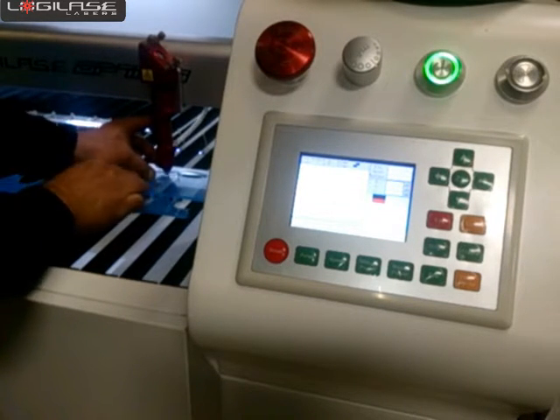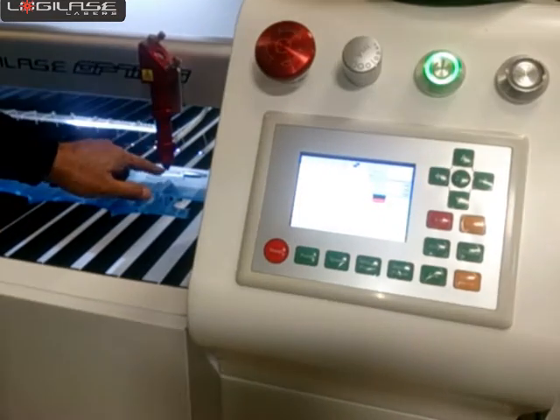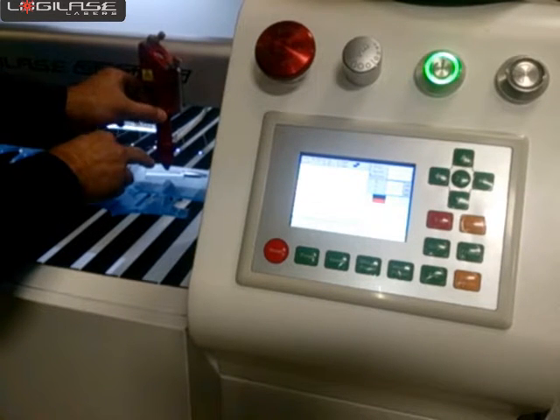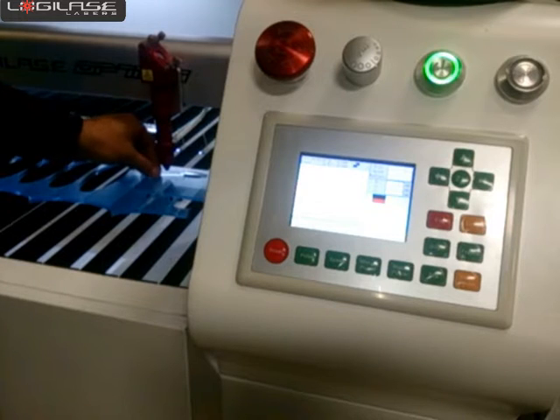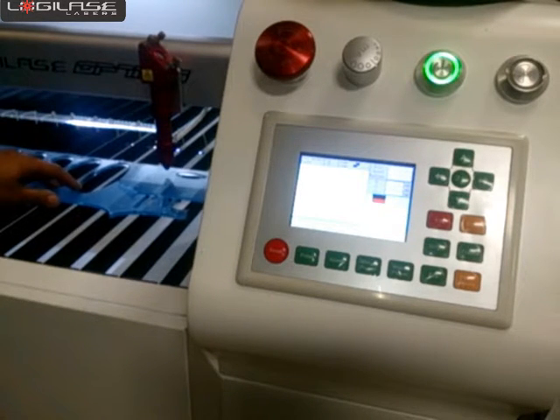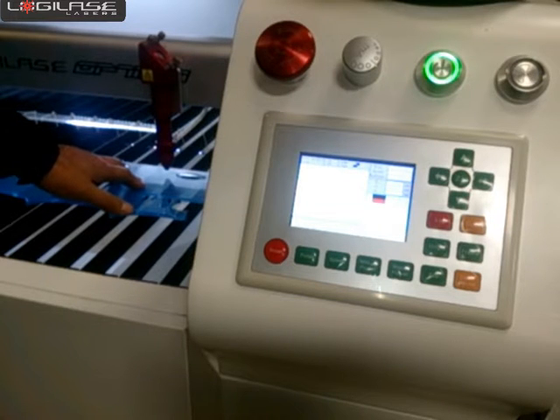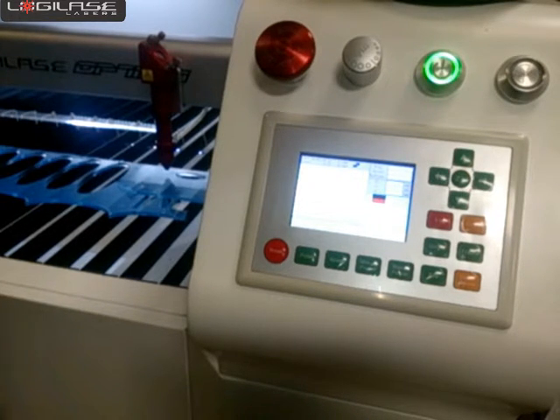You can place it underneath the nozzle, and while it's there, you can tighten the thumb screw. So this is the focal adjustment. For any particular material of the same thickness, if you want to do a repeat job, you don't need to repeat this step. As long as the material thickness is the same, you can skip this step. Otherwise, if you change the material, then you have to do this focal distance adjustment once you have a different material.